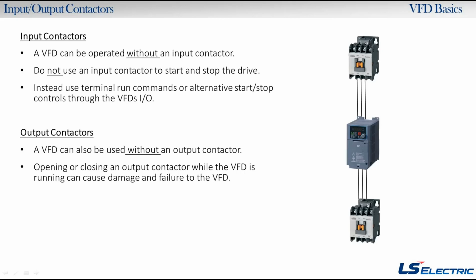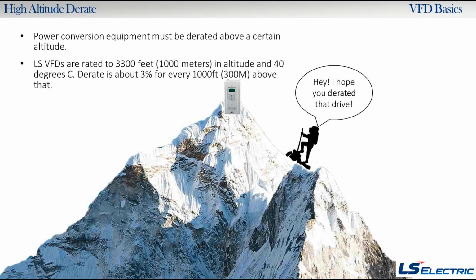All right, here's a little bit about high altitude derate. So this is the inverter, or the drive's power conversion equipment. The air is thinner higher up, so you have to derate the drive. So this might come up for you guys in Denver, Colorado. We've got a few guys out there that might do this occasionally if you're up on a mountain. The drives are rated where you don't need any derate up to 1,000 meters, but when you go past that, there's a 3% derate for every 1,000 feet, or 300 meters.